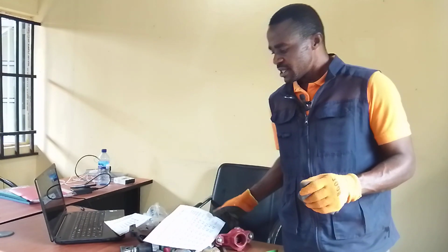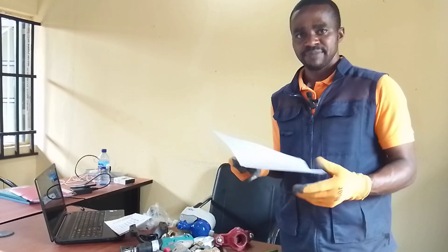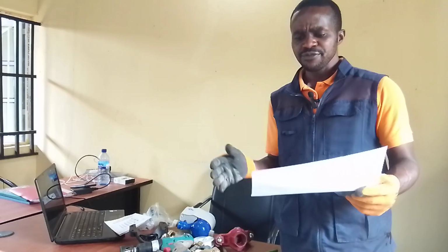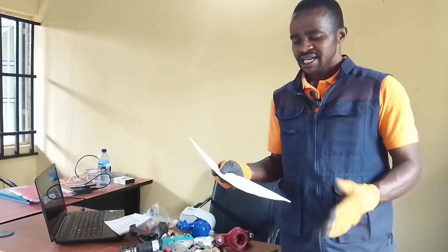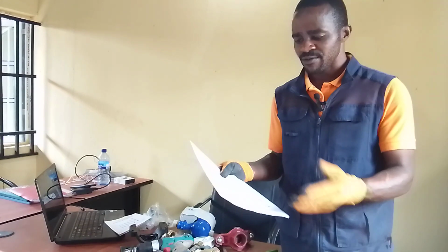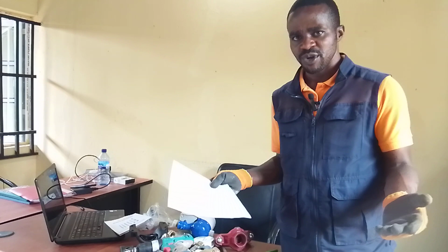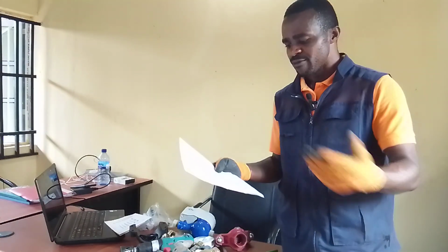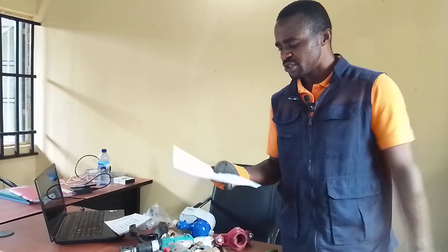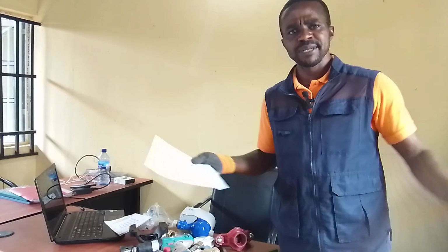All right, this is what you must do. It is the same way when somebody says to you, I bought some materials, I have wire. You ask the person what's the size of the wire. He tells you I have, say, 2 millimeter squared, or I have 1.5 millimeter squared, and I want to install a 2 horsepower pump. Simply tell him that it won't work.